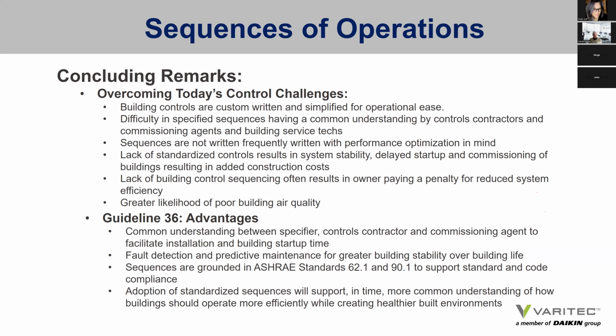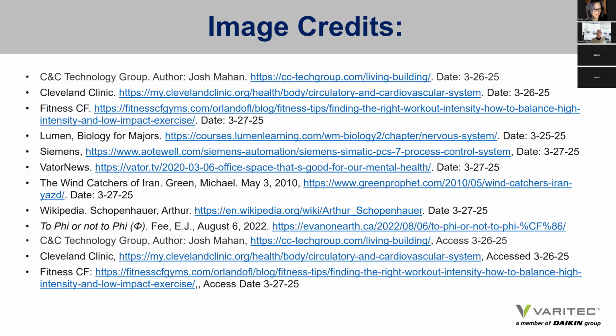So the advantages of the guideline are common understanding between specifier, controls contractor, and commissioning agent, fault detection and predictive maintenance included so the owner can service equipment before catastrophic failure, offering greater stability. Sequences grounded in Standard 62.1 and 90.1 to assure indoor air quality and energy efficiency. And adoption of the standardized sequences will support, in time, more common understanding of how buildings should operate more efficiently while creating healthier built environments.